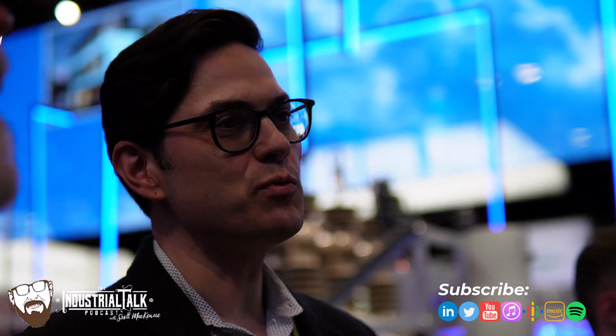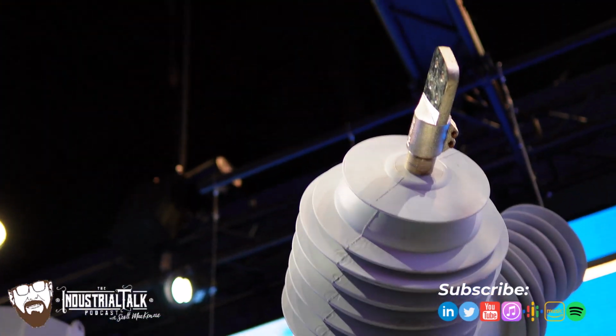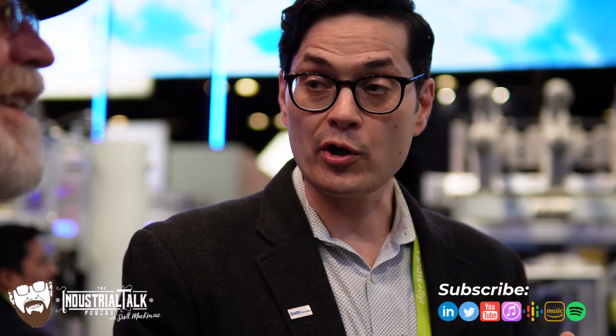All right. Beautiful. So this is one of our most recent innovations. So this is a 72 kV, and we've been calling this the Viper HV. It has the ability to do reclosing. So this thing is fully tested for a 4-shot sequence per the C37.60 standard. But this is a device that's got the flexibility to be used in multiple ways. So yes, it does do reclosing, but I don't think too many people are going to be doing reclosing at 72 kV. You can do overcurrent protection with this device. It does have the ability to do a lot of what a circuit breaker does.